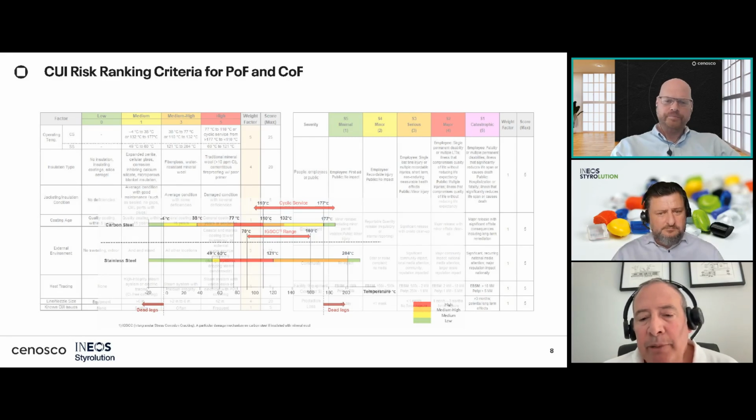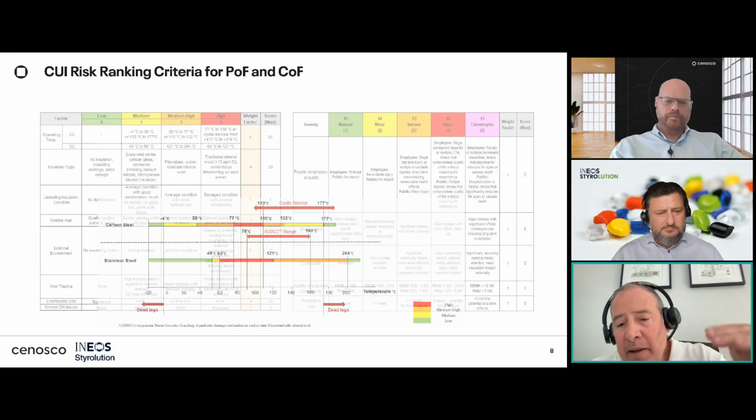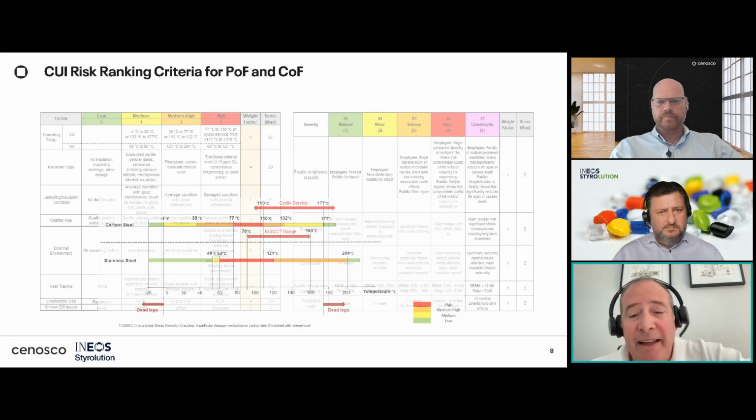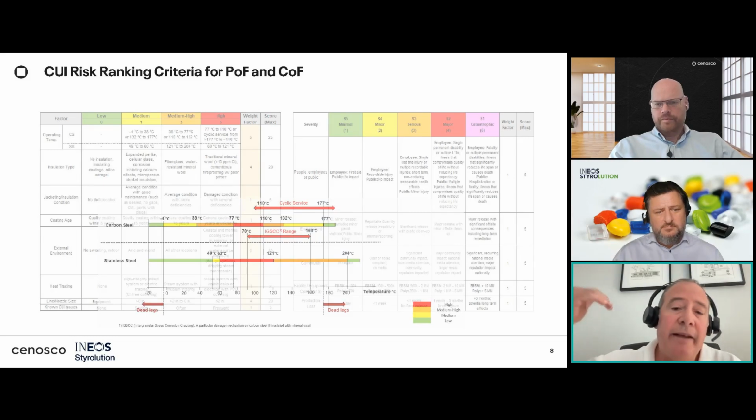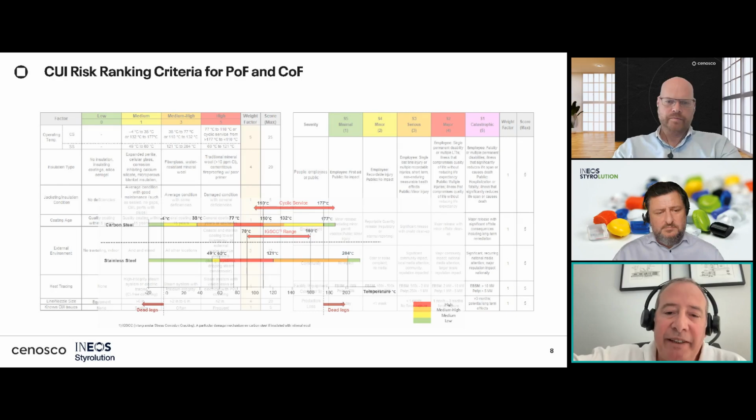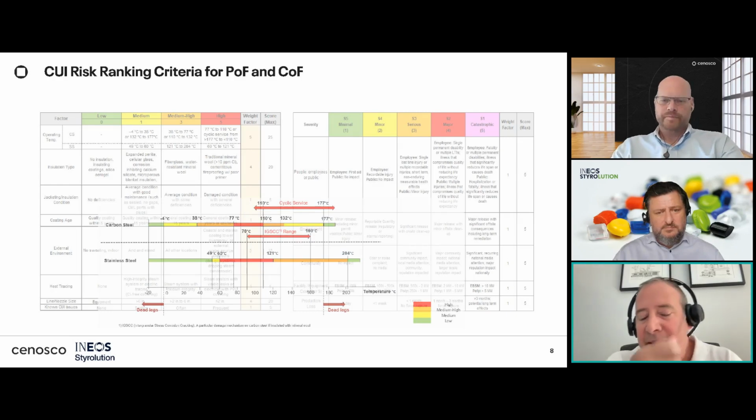Yeah, but here's the thing. You can put a sensor today, okay? And maybe you don't see any moisture today, but the corrosion has been happening for 10, 15 years, okay? And it might leak even if it doesn't have much moisture today. You might have other areas that have higher moisture level, but the coating is intact, okay? So just adding a sensor right now, it doesn't tell you the story on the last 20 years of that piping system, okay? So yes, sensor will help you see from today moving forward, okay, how much moisture you have. It's not gonna tell you how's the coating in that area.